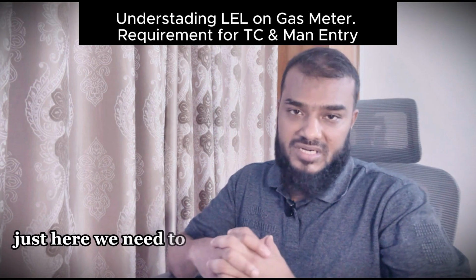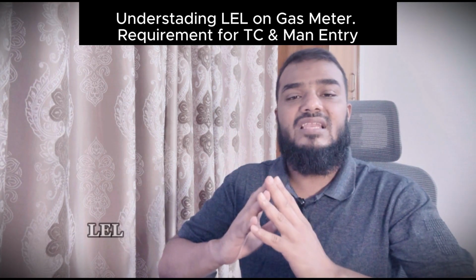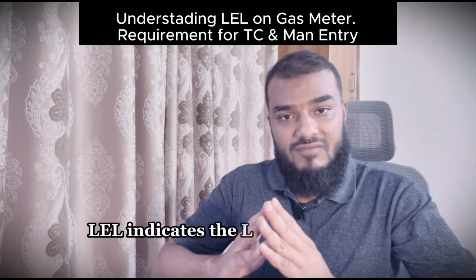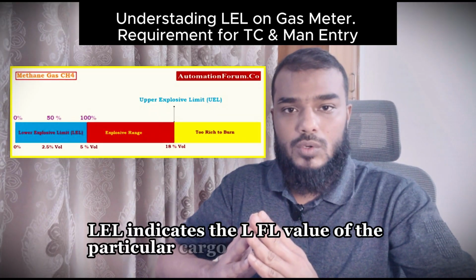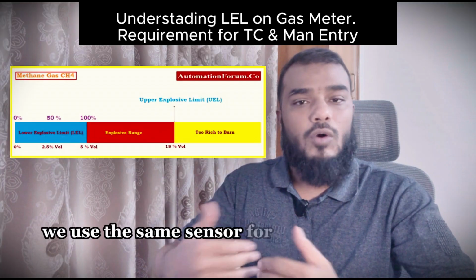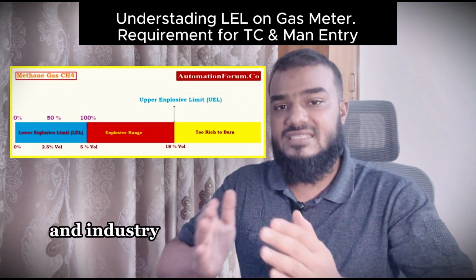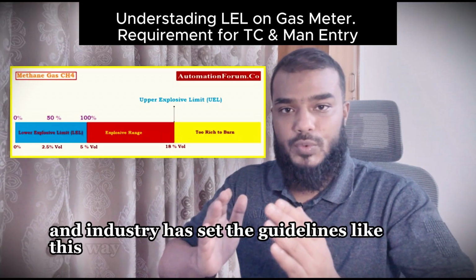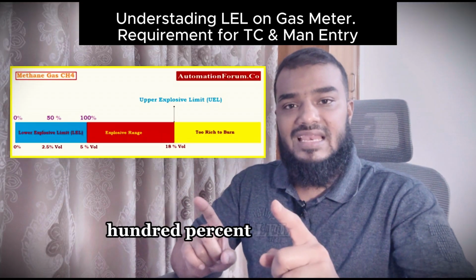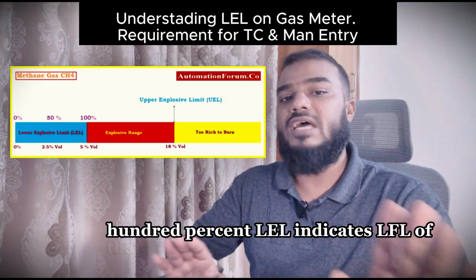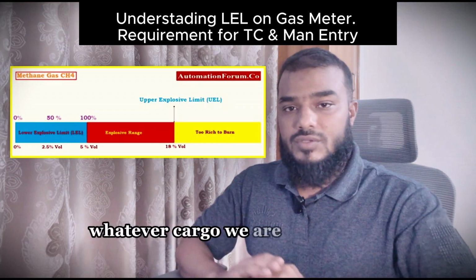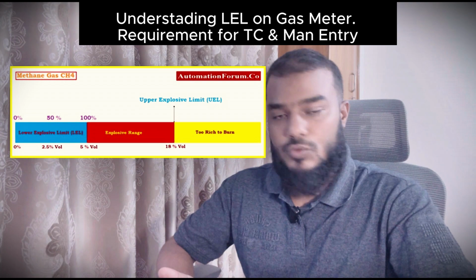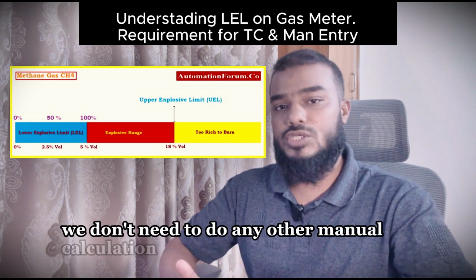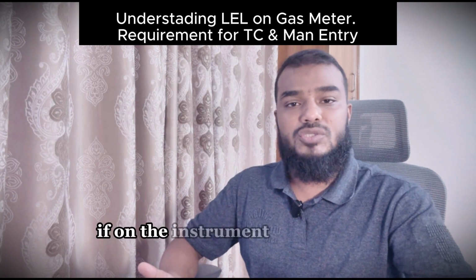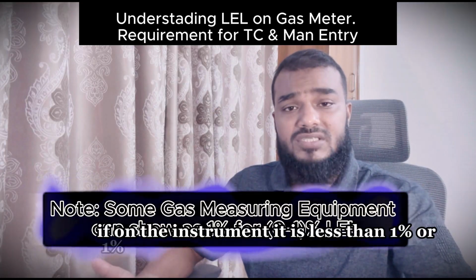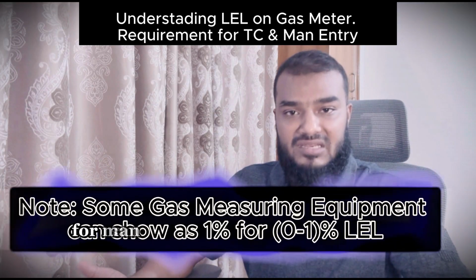Here we need to understand that 100% LEL indicates the LFL value of the particular cargo. We use the same sensor for all the cargos, and industry has set the guidelines this way. Whatever cargo we are talking about, we don't need to do any other manual calculation. If the instrument shows less than 1% or 1%, we can accept it for man entry.